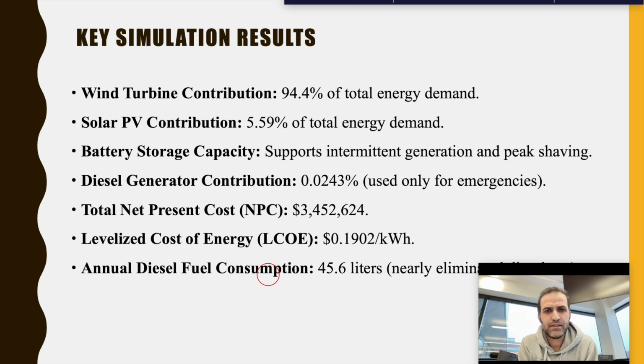Battery storage capacity supports intermittent generation and peak shaving. Diesel generator contribution is a backup profile used only for emergencies, around 0.02%. Total net present cost of this project is around $3.5 million Canadian. Levelized cost of energy, LCOE, is around 20 cents per kilowatt hour. Annual diesel fuel consumption is around 45.6 liters, nearly eliminated, essentially nothing.